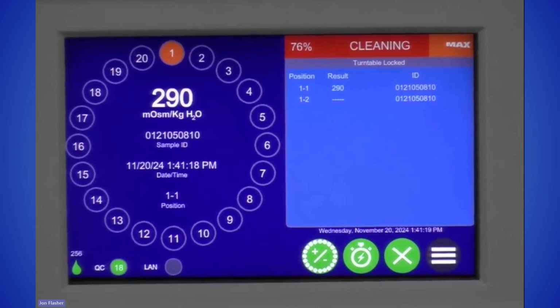So we've aspirated the sample. We brought it into the sample chamber. We performed a freezing point depression measurement within the sample chamber, and we got our first result. It came right in at 290, which makes a whole lot of sense because I just put some 290 in a tube off to the side over here to use as my patient sample. So that came in right on the money at 290.